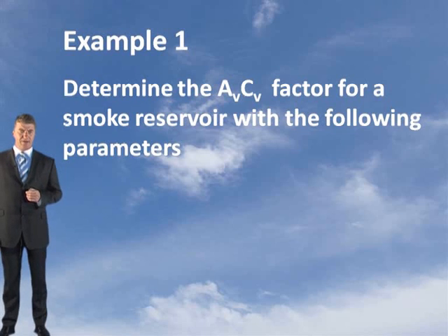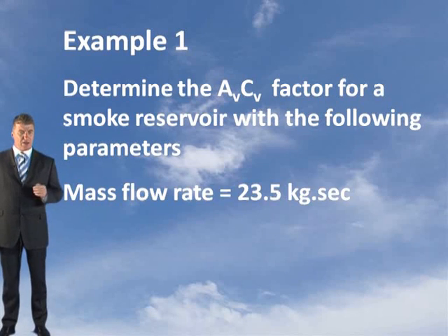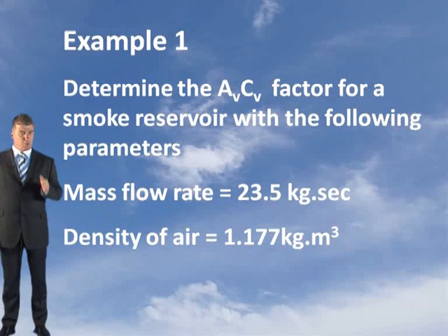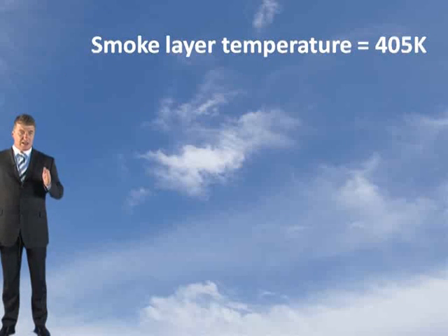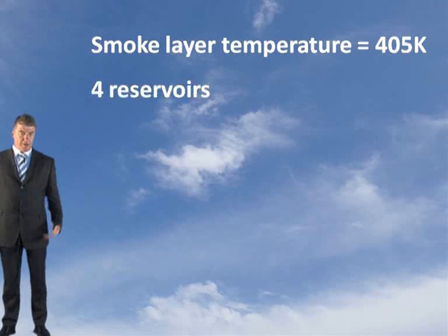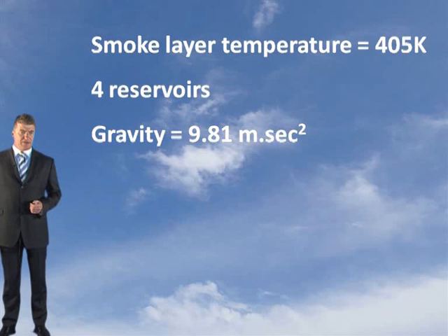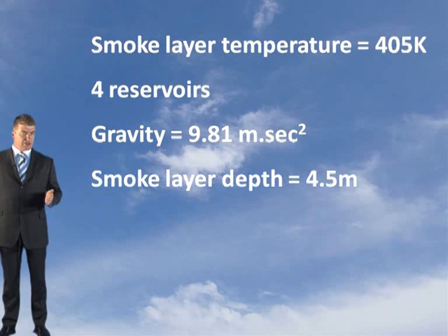Determine the AVCV factor for a smoke reservoir with the following parameters. Your mass flow rate of smoke is 23.5 kilograms per second. The density of air can be taken as 1.177 kilograms per meter cubed. The temperature of the smoke layer is 405 degrees Kelvin. The building has four reservoirs. Acceleration due to gravity can be taken as 9.81 meters per second squared. Your smoke layer depth is 4.5 meters.